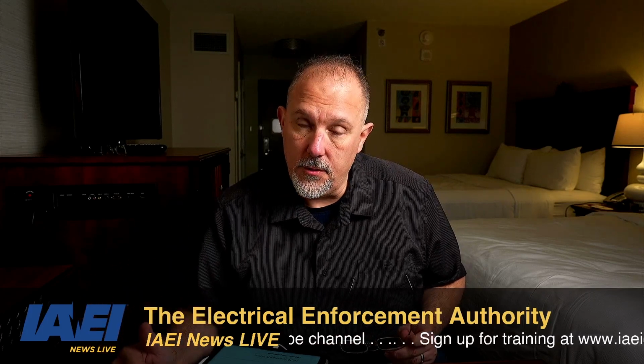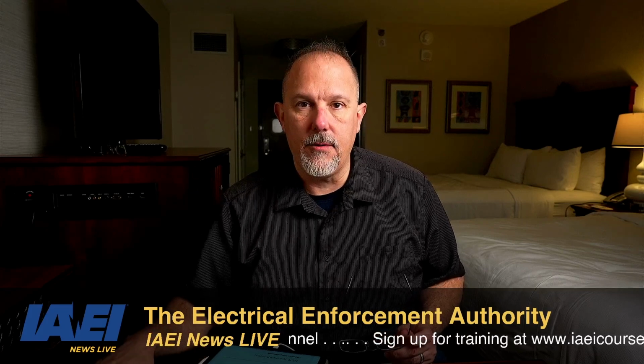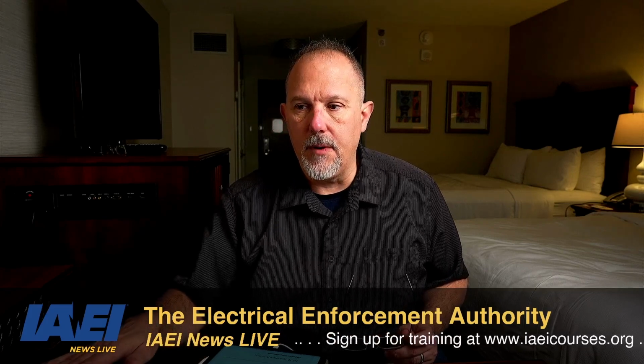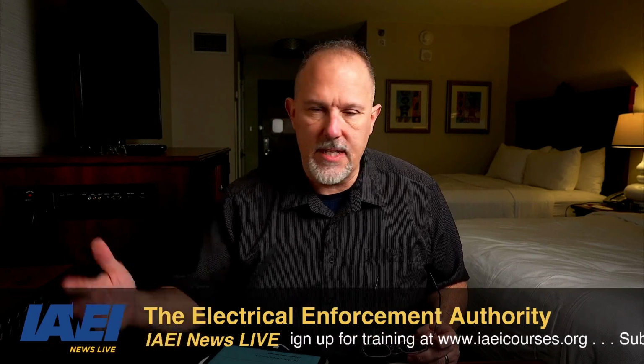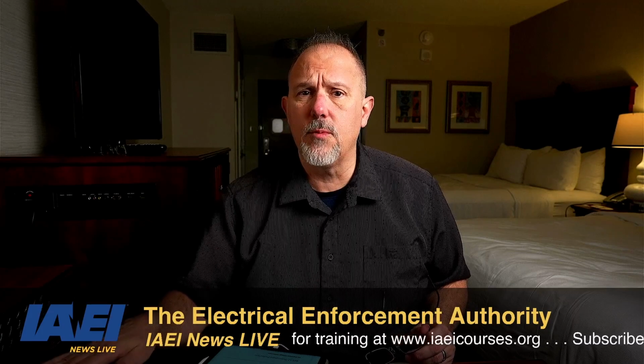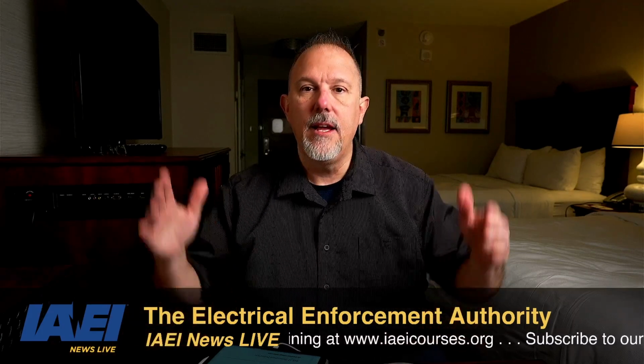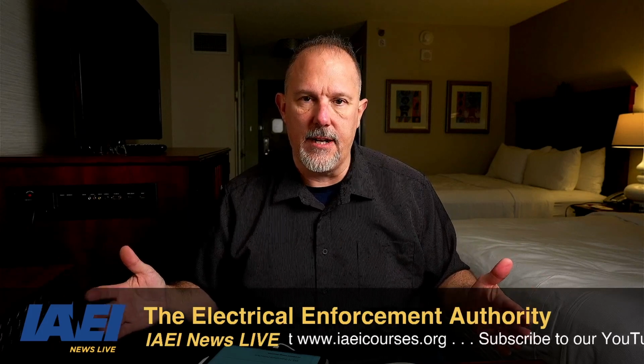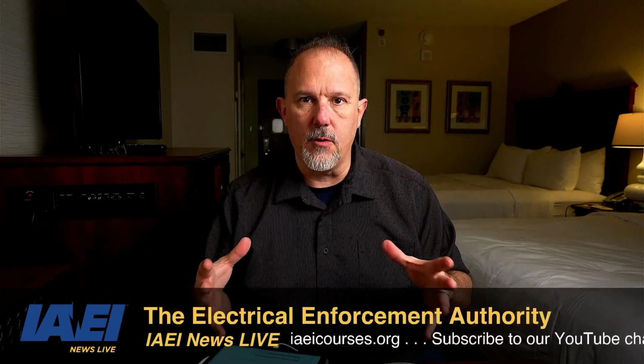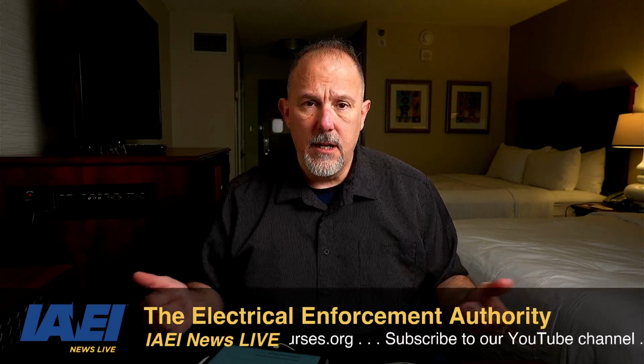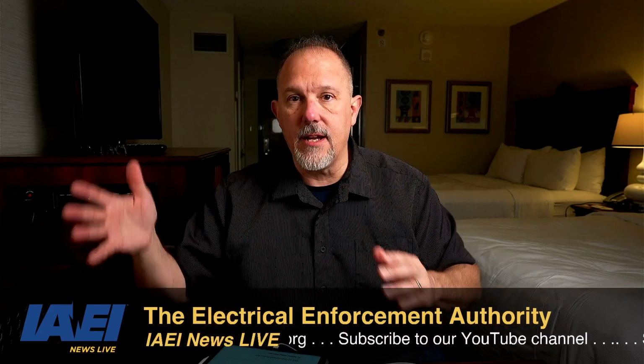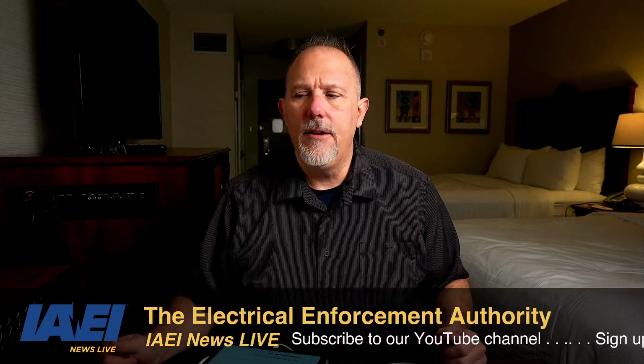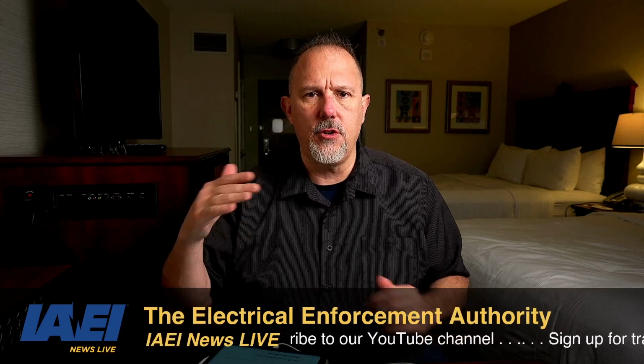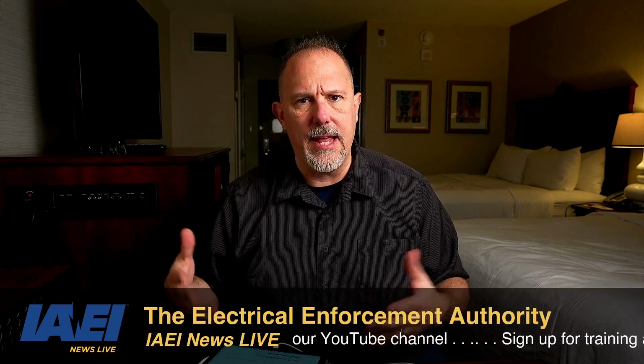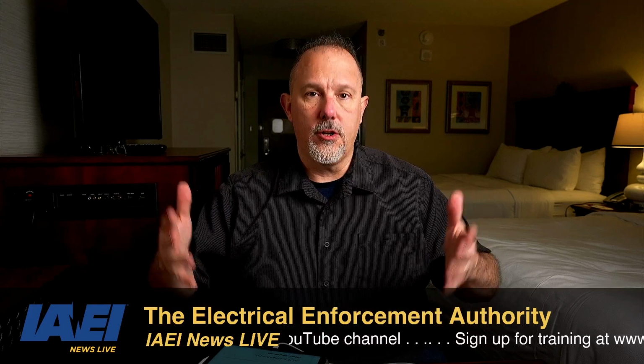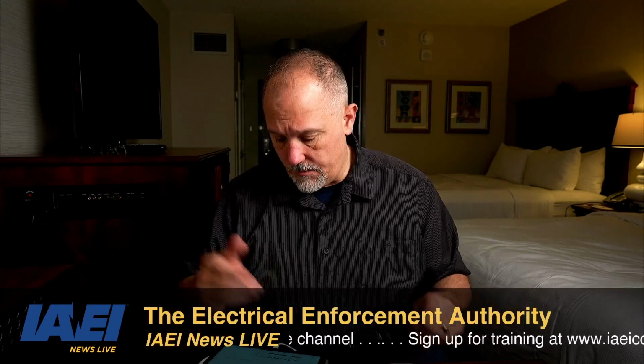And that's important too. That's important to tell you how it's basically going to be used. Is it always going to be running? Is it going to be relied on temporarily? Because what they'll do, if it's always relied on, if you say this is going to always be on for extended periods of time, they're going to derate some things from a generator perspective, because you got to think about the heat. If it's only going to be used for short periods of time whenever you lose power or whatever, then you'll probably have a little bit larger. You can adjust the kVA rating of that generator, the output, because you're not going to be running it for an extended period of time. So just keep that in mind.